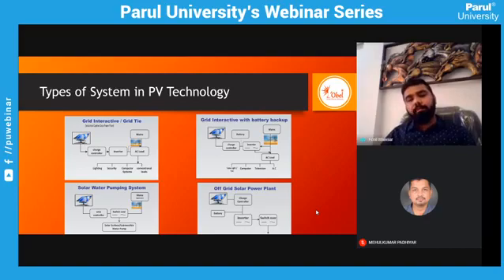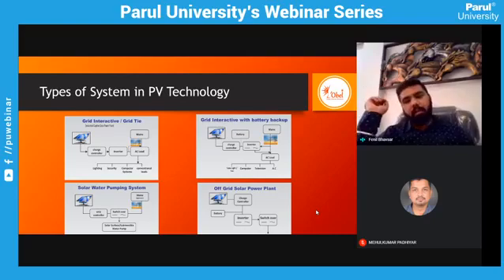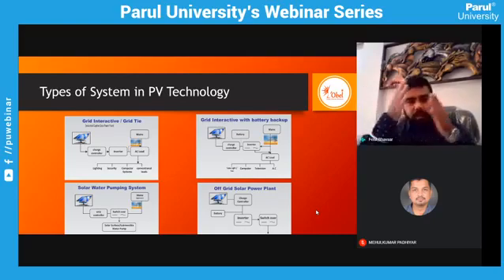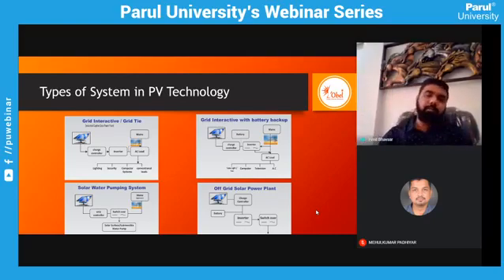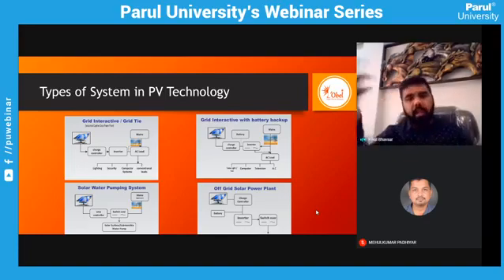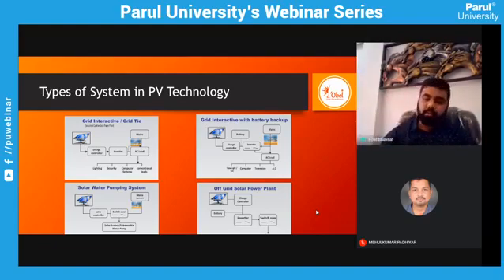For this reason, solar gets first priority through the load while generating power and giving it to the load. So this was the brief about the grid interactive grid tie system, which is also called a solar captive power plant. Another type is grid interactive with battery backup. This system is the same as the grid interactive grid tie system, with the only additional portion being the battery. This system is also known as a hybrid system.